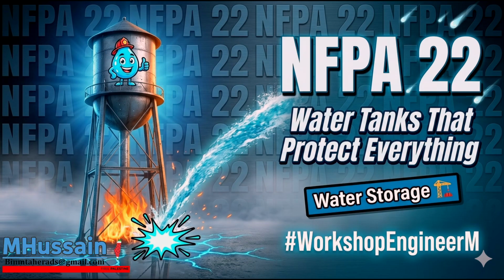Oh, they absolutely will. But as the safety engineer, your responsibility is risk mitigation. And municipal infrastructure is a massive, uncontrollable variable. But it's old. Partly, yes. Those 36-inch mains in major cities are often 80 to 100 years old. They're cast iron, they're brittle, and they fail catastrophically. That makes sense. Plus, municipalities constantly reroute water, throttle valves, or lower system-wide pressures to reduce leakage rates in their aging pipes. So the pressure you measured last year might not be there today. Exactly. If you tie your life safety system directly to that grid without a buffer, you are inheriting 100% of their hidden vulnerabilities. A private tank isolates your facility from external failures. You're buying control over your own hydraulic destiny. Control over the variables. I like that.